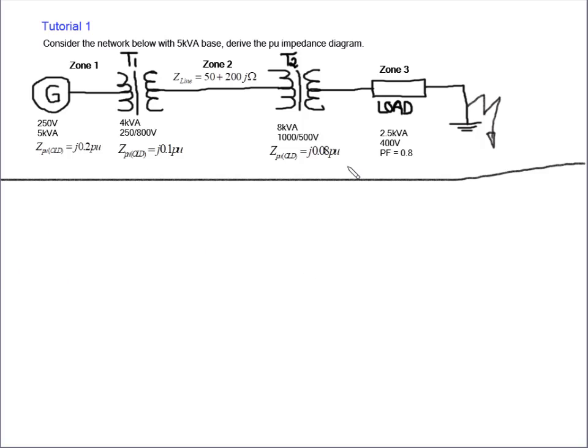We've given the per unit voltage, the old per unit for each component. So the generator got an old per unit of 0.2, the transformer 0.1, and so forth. So the general formula of per unit calculation is based on using the old values so that we can work on a new value, because the new value will be worked based on the new volt ampere value that is given. This is why you change from the old to the new, because you are working on a different base now.